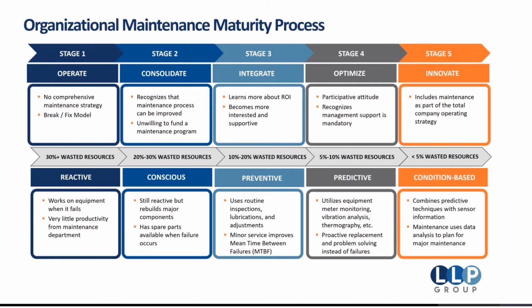Using this data and the machine learning features built into the underlying operating service, you can move to a predictive maintenance model that allows you to analyze common failure points and anticipate when a particular piece of equipment is likely to break based on hours of service or other factors. The main focus is to reduce wasted resources to achieve peak efficiency and the best possible return on investment on every single asset. This means that accurate real-life data needs to be used to manage the entire life cycle of the assets.